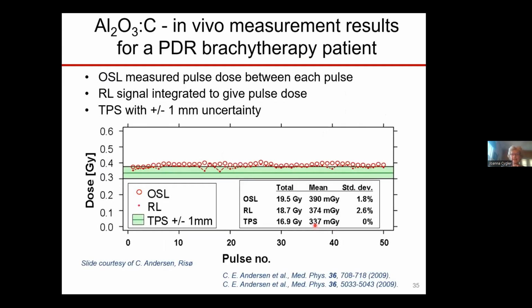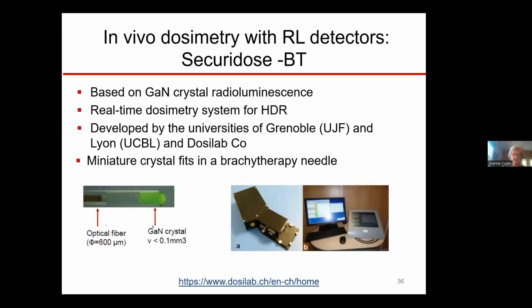So this slide shows an example of how they use this system for pulse dose rate brachytherapy treatments. We see the radioluminescent signal that was integrated over the pulse in those small red dots. The open circles are the OSL signal that was measured after each pulse. And we see that they actually agree very well with treatment planning calculations, within plus or minus 1 millimeter uncertainty. So that's a very encouraging detector and system.